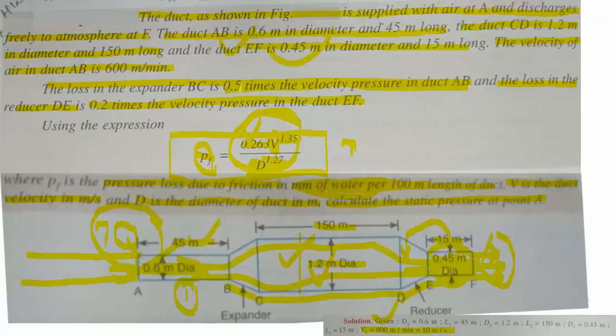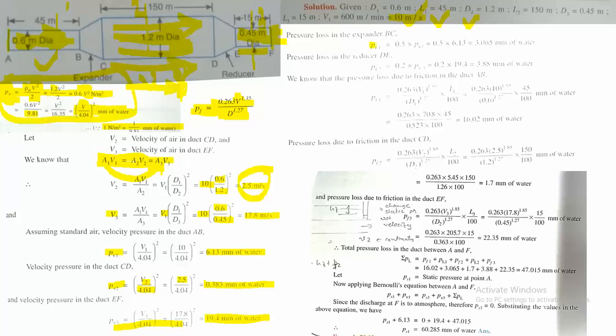The pressure loss in section BC is 0.5 times the velocity pressure head in AB. So loss in BC = 0.5 × PV1 = 0.5 × 6.13 = 3.065 mm of water. The BC section pressure loss is now completed.